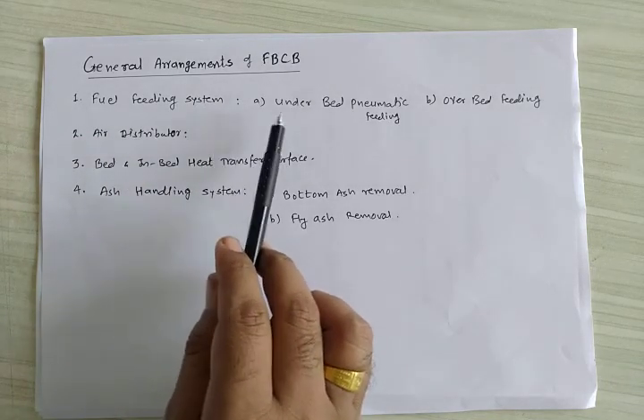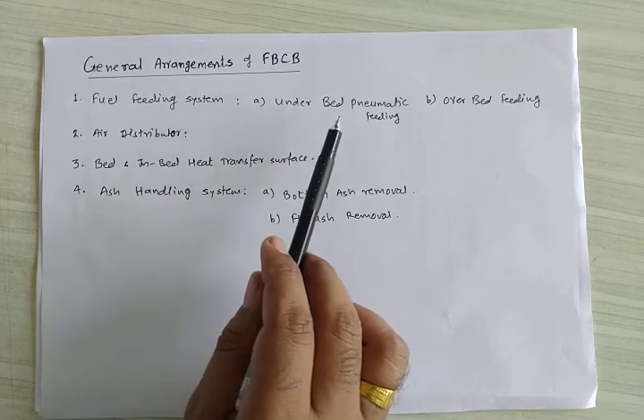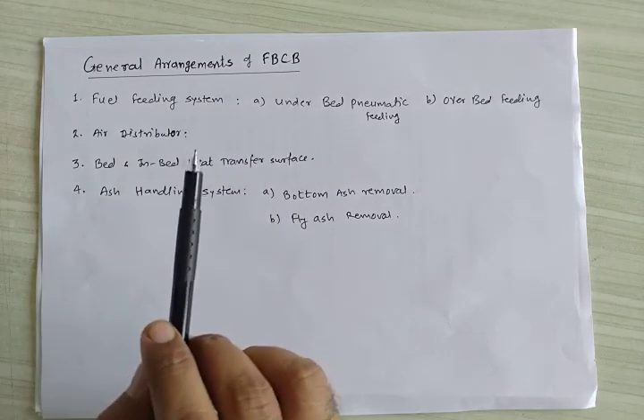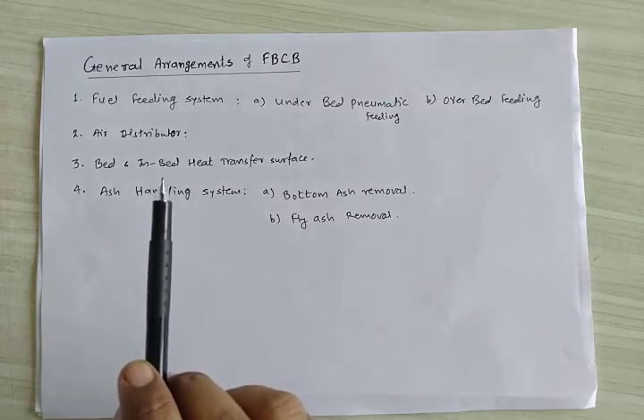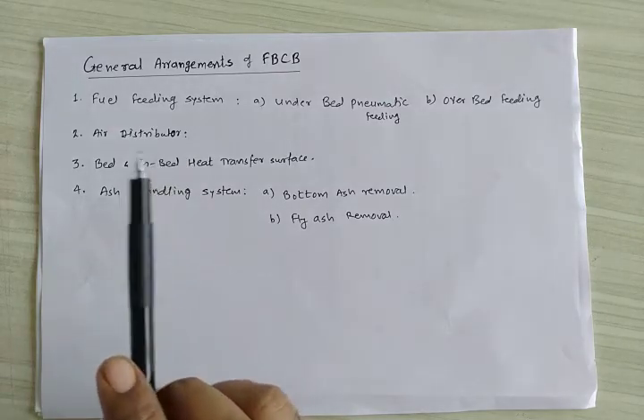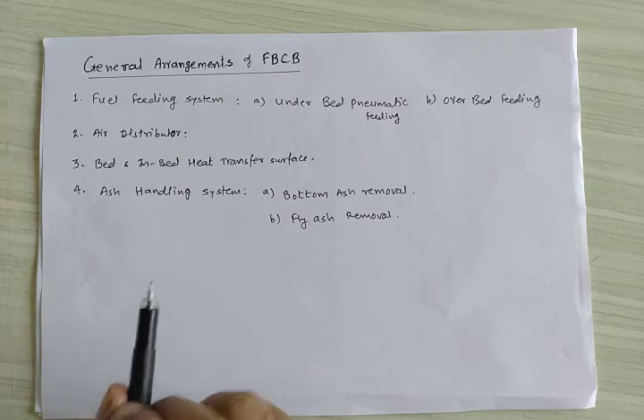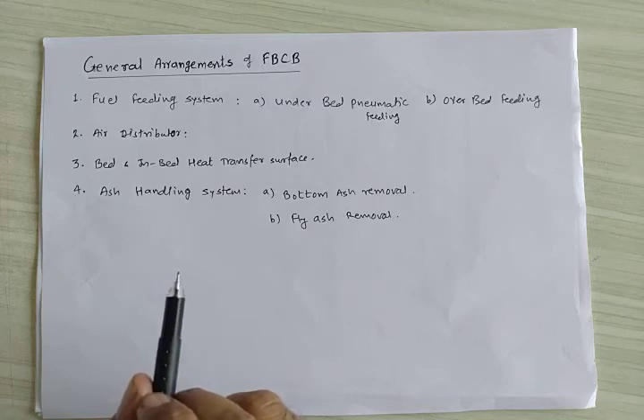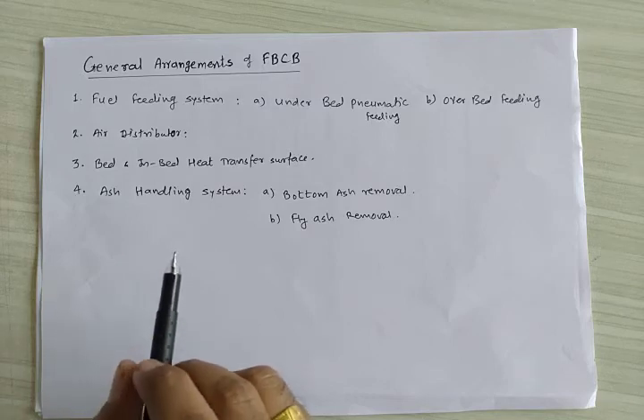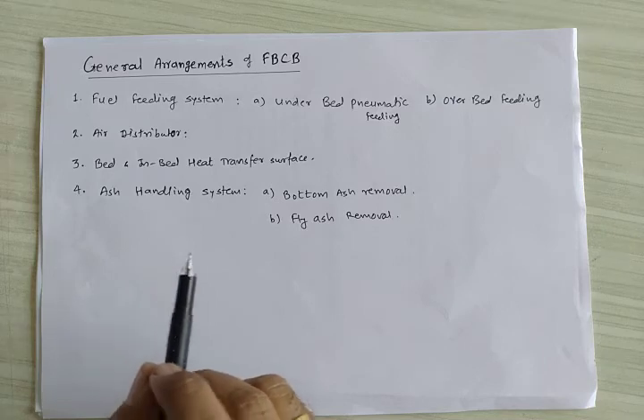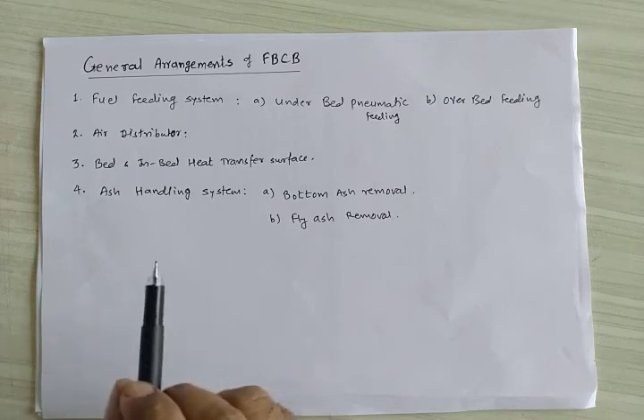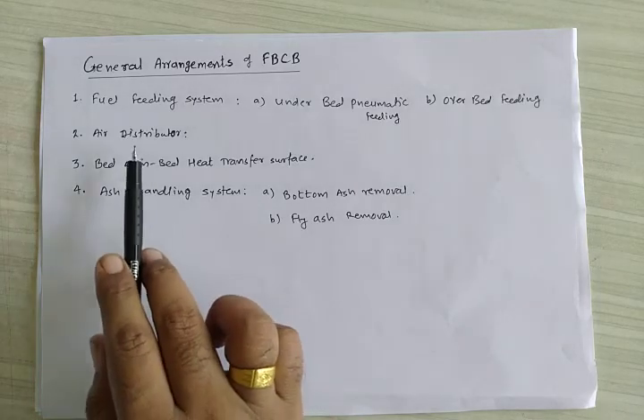In the fuel feeding system, the first type is under-bed pneumatic feeding, where coal is crushed to a size of 1 to 6 mm and pneumatically transported from the feed hopper. The second type is over-bed feeding, which accepts oversize fuel, eliminates the transport line compared to under-bed feeding, and accepts coal of size 6 to 10 mm.